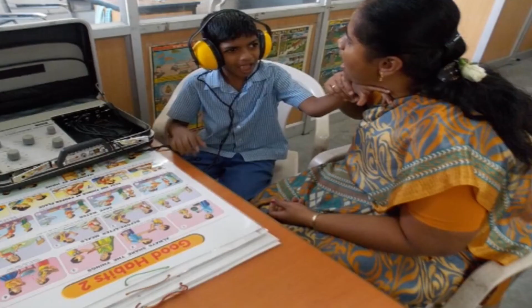The teacher's microphone picks up the sound signal. Here, the signal is the teacher's speech, and it is converted into an electrical signal. This electrical signal is transmitted to the amplifier, where it is amplified and delivered to the student control boxes. The student control boxes can be adjusted as per the amplification need of each user in individual ears. The amplified electrical signal is then converted to an acoustic signal by the receiver in the headphones and delivered to the ears of children with hearing impairment.